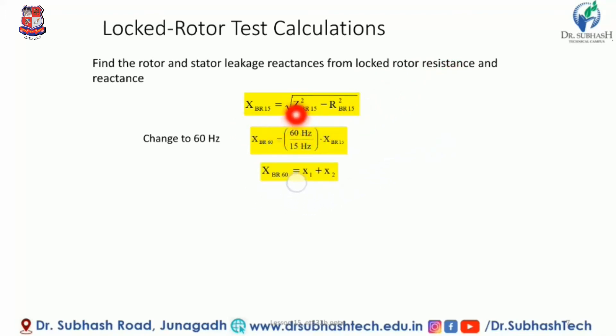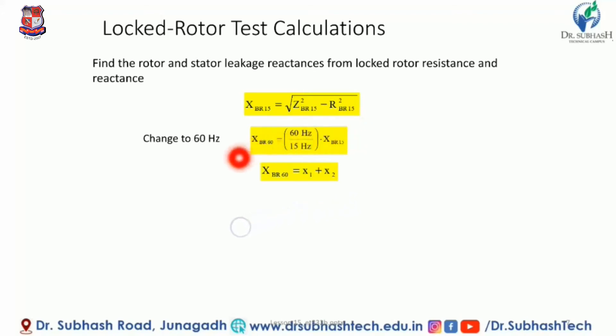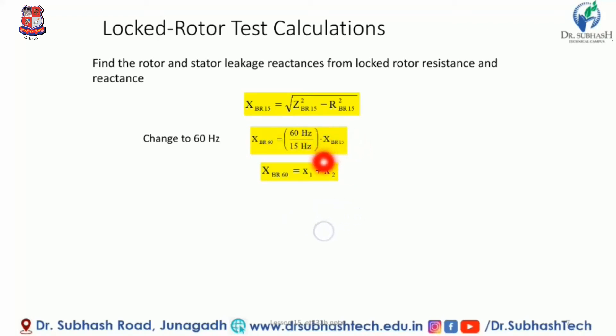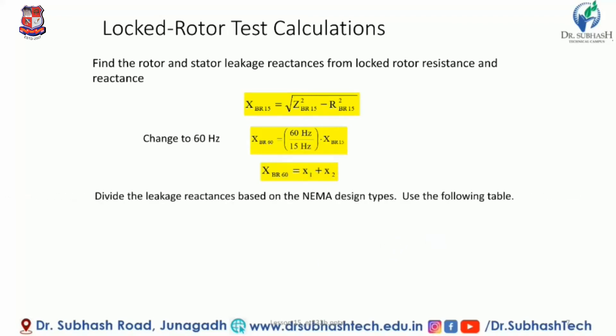The blocked rotor resistance is: R_BR = Z_BR15² − X_BR15², and X_BR = √(Z_BR15² − R_BR15²). To convert to the rated frequency of 60 Hz: X_BR60 = (60/15) × X_BR15. Then X_BR60 = X1 + X2, giving the combined stator and rotor leakage reactance values.